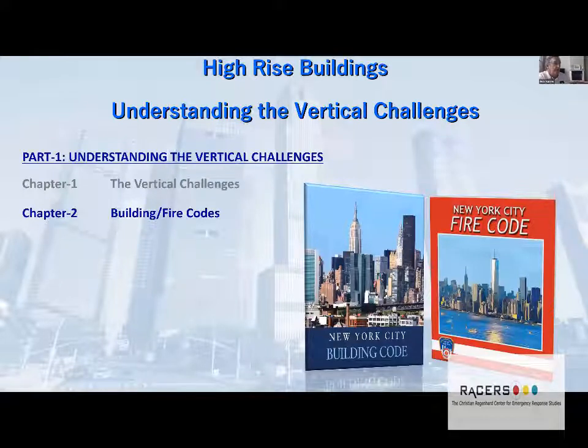In taming the fire environment, sprinklers or not, today there are still high-rise buildings, not only in the United States but globally, that were constructed under old building and fire codes and still do not have sprinklers, remaining unsprinkled structures. In the code industry today, this is called the grandfather clause: if an existing building continues without change, it is maintained in accordance with the code when it was constructed. Recently, the NFPA high-rise task force for building safety, which Charles and I sit on, introduced into Life Safety 101's new edition, particularly the existing section, that high-rise buildings shall be sprinkled. So now it's in a standard, and we have to bring that into codification.